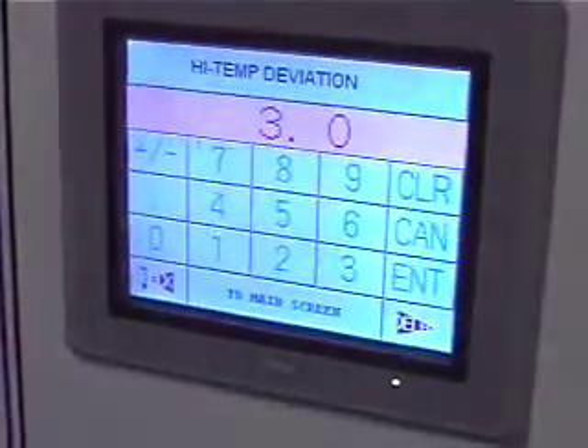So essentially what we're telling you, anything over 3 degrees above set point is going to initiate a high temperature. Okay? If we're set at 4 degrees and you get to 7.1 degrees, it's going to register on the status line on the main screen: high temperature. You've got a high temperature situation, but you haven't de-energized your remote alarms. You haven't caused this to go off. None of that's happened until after the delay period. So if it's hovering right there and going in and out of alarm, if it's set at 10 minutes, it has to be a full 10-minute delay period before anything actually happens.